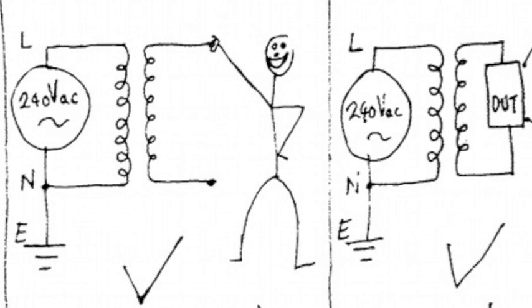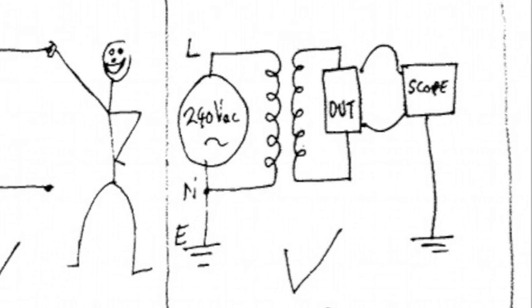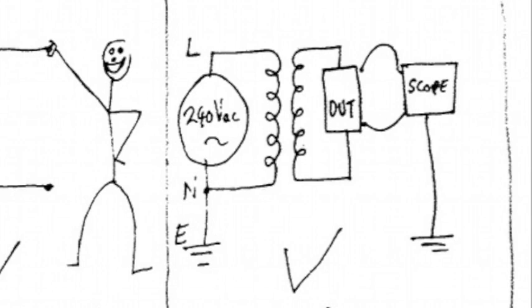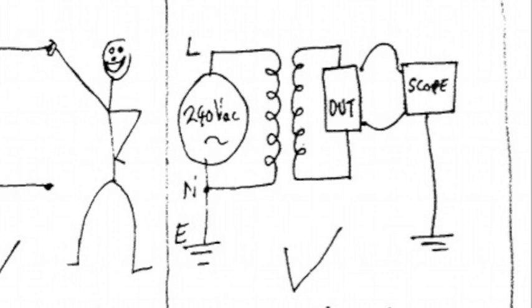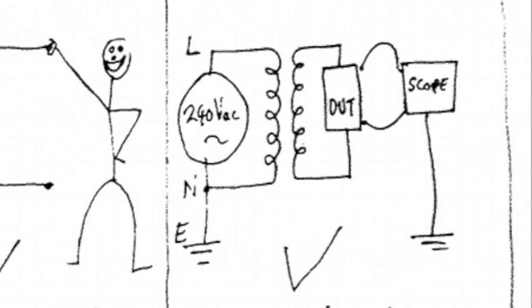As an example of testing equipment, let's look at this diagram. Here we've got a scope. The device under test, DUT, is connected via the isolation transformer, and we've got the oscilloscope leads probing across the device under test. This means the scope is protected because that whole circuit is isolated from earth, so current can't pass through the scope from the unit. The scope itself is protected, just like the person was protected, because the circuit is completely isolated from earth. That's what an isolation transformer can do for you: it can protect your instruments, it can protect you.